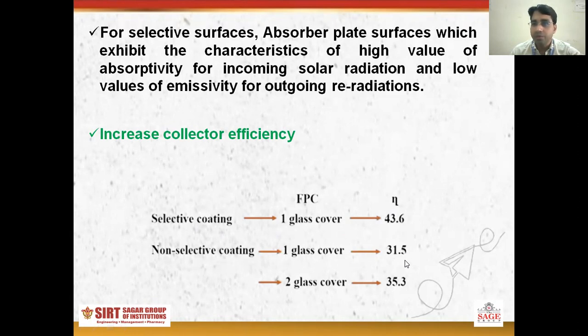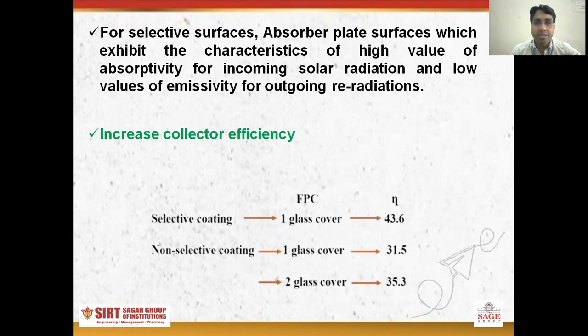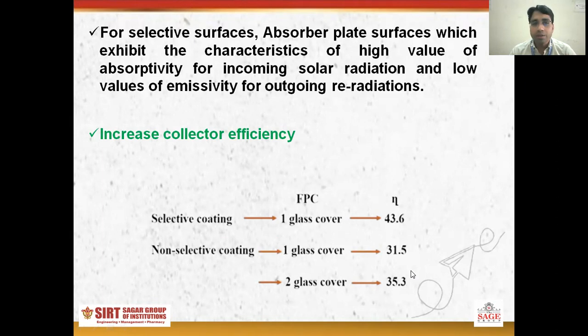In the case of non-selective coating with one glass cover, the efficiency is 31.5 percent, but with two glass covers this efficiency increases to approximately 35.3 percent. However, if we increase to three glass covers, the efficiency may again decrease. So this covers selective type and non-selective type coatings.